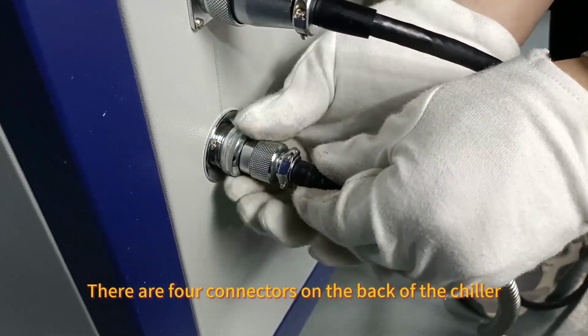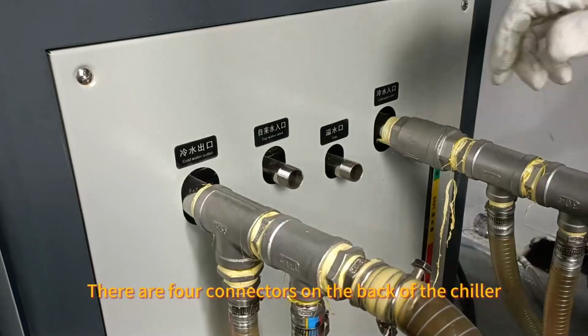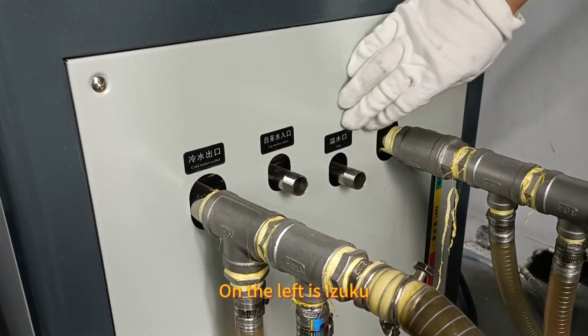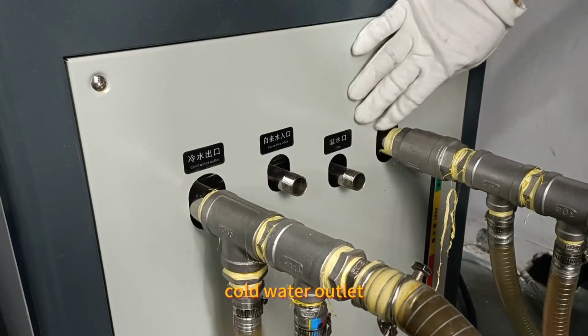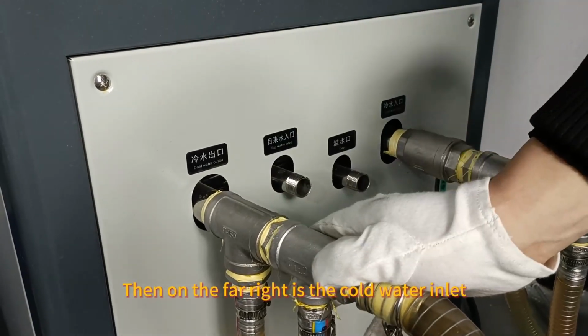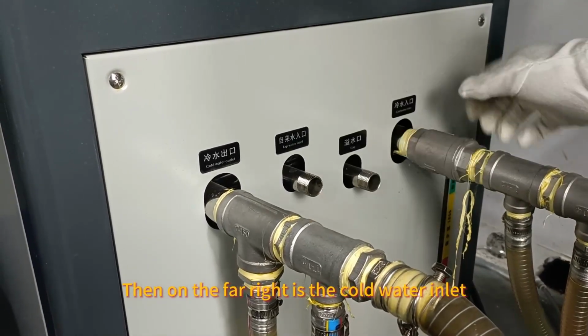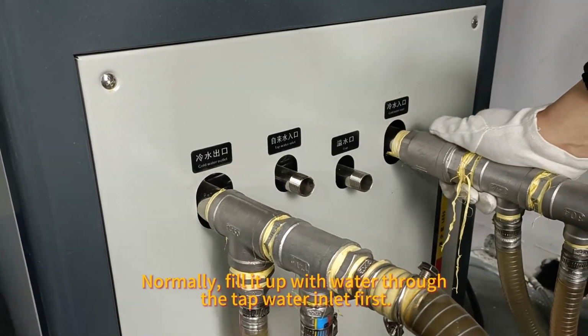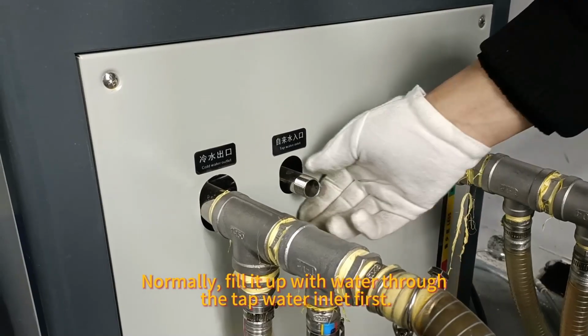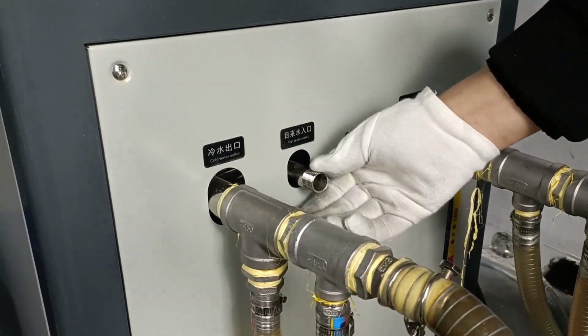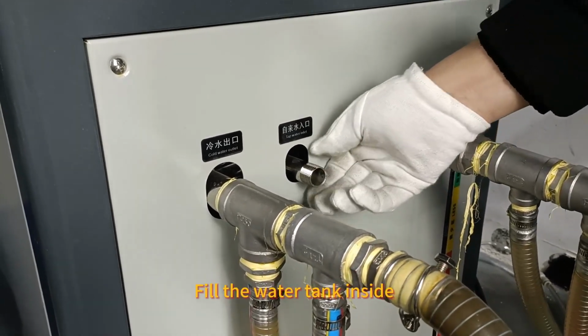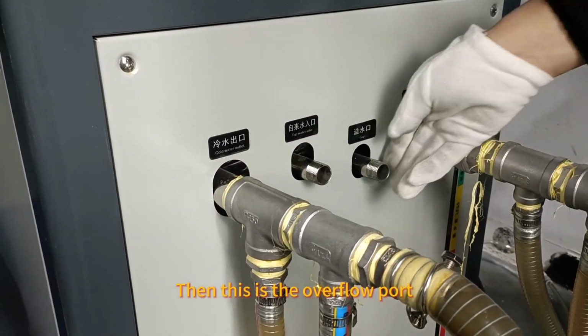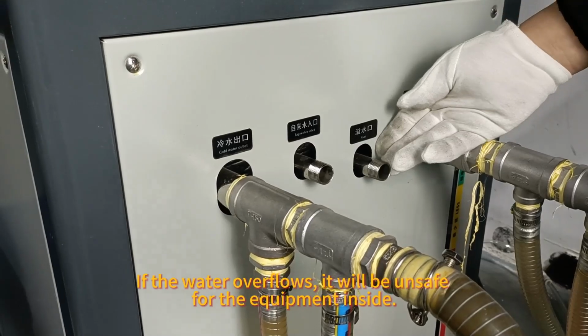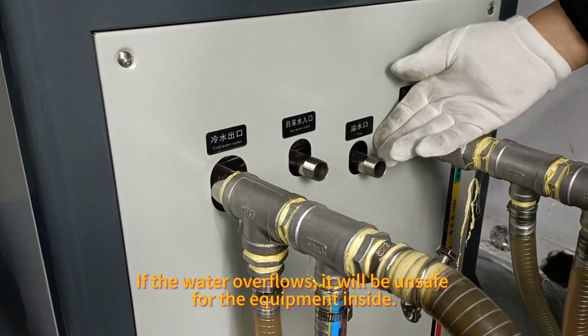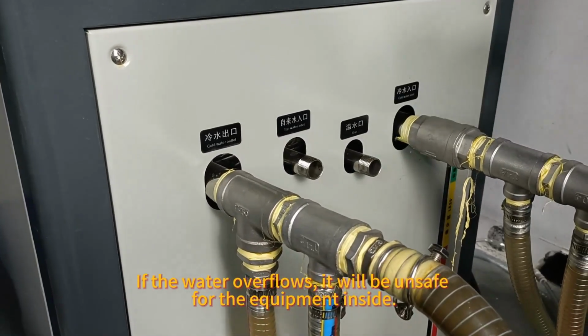There are 4 connectors on the back of the chiller. On the left is the cold water outlet. Then on the far right is the cold water inlet. Normally, fill it up with water through the tap water inlet first. Fill the water tank inside. Then this is the overflow port. If the water overflows, it will be unsafe for the equipment inside.